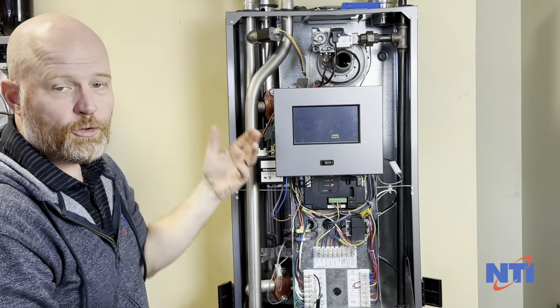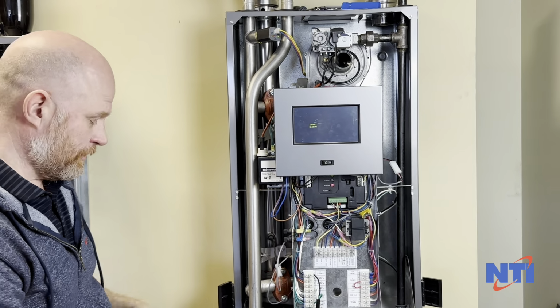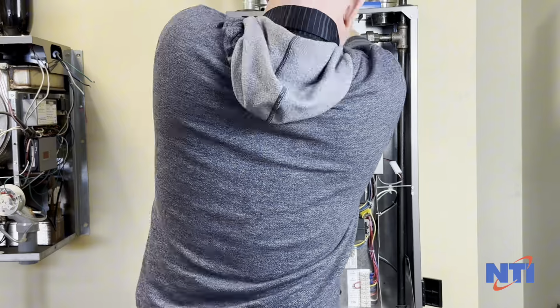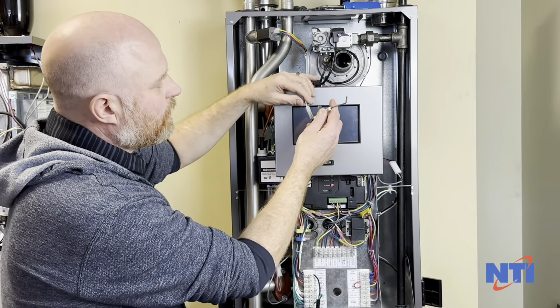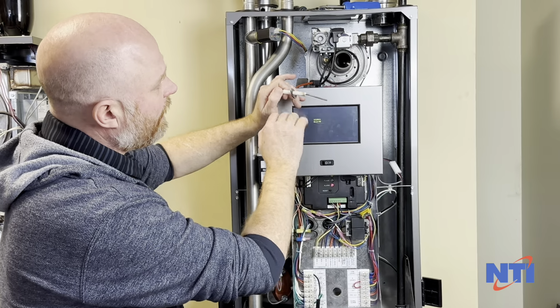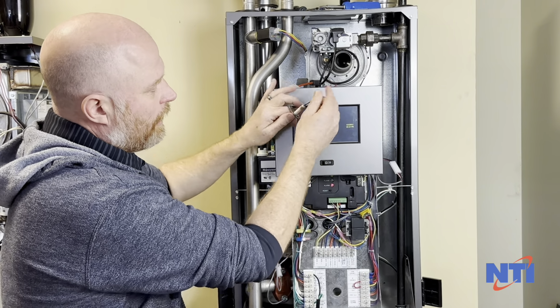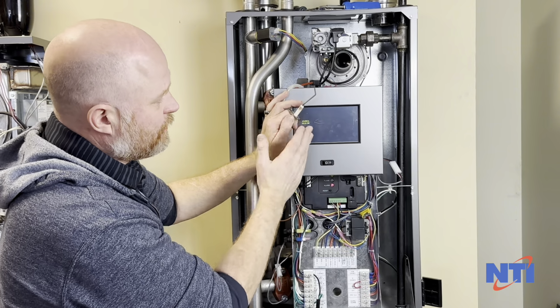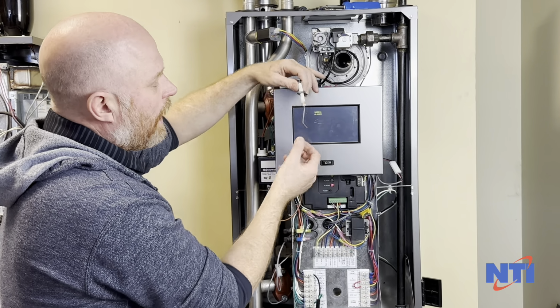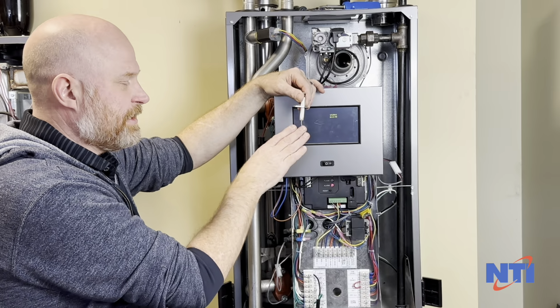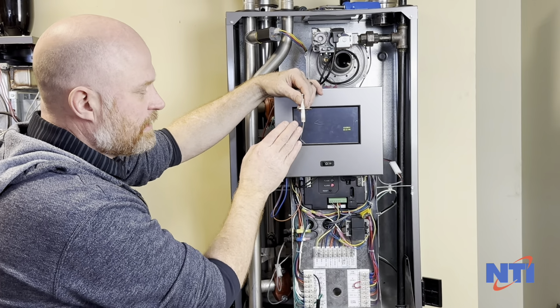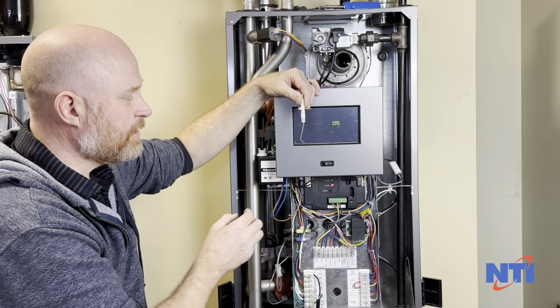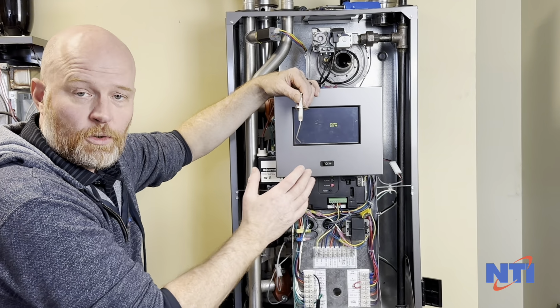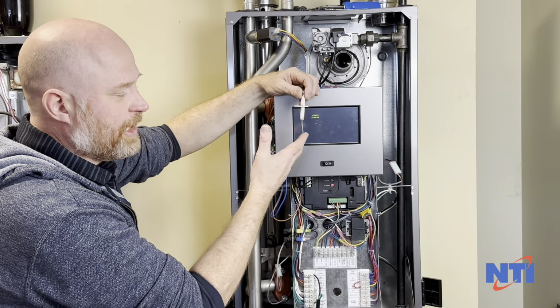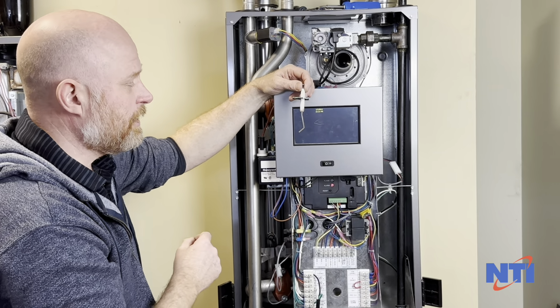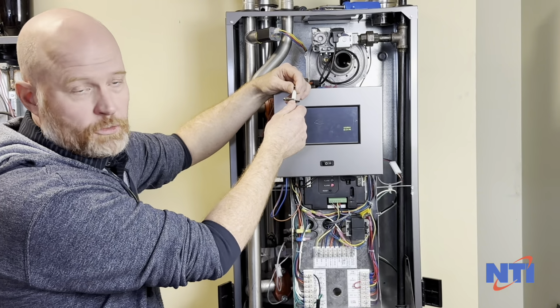So the first thing we're going to want to do is pull the flame probe out and just give it an inspection, make sure it's in good condition. So once you get your flame rod out, you're looking for any signs of cracking or damage to the ceramic here. You want to look at this little hockey stick shape on the TFT boilers at least and make sure that it's nice and straight. Generally speaking, I don't worry too much about the discoloration of the rod. I've seen rods that look perfect like this that don't work, and I've seen ones that are really crusty and dirty that actually work very, very well. If you're at all concerned, your best bet is just to replace this and put a new one in. They are wearable items, and over the course of several years, it is just going to wear out.